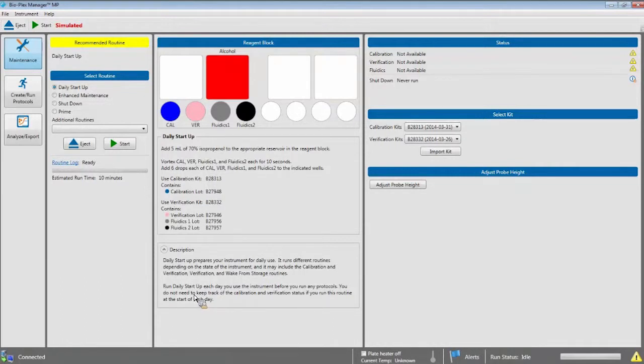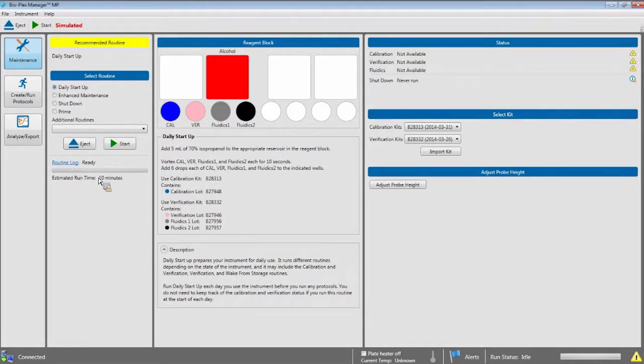When you open the Bio-Plex Manager MP software, it opens on the maintenance page so you can prepare the MagPix to run your assays and make sure it's calibrated for optimal performance. On the left side of the page, there are three buttons to take you directly to the three main performance functions in the software. These buttons appear in each section of the software. The maintenance section is where you run your startup, shutdown, calibration, verification, probe height adjustment, and other maintenance routines.